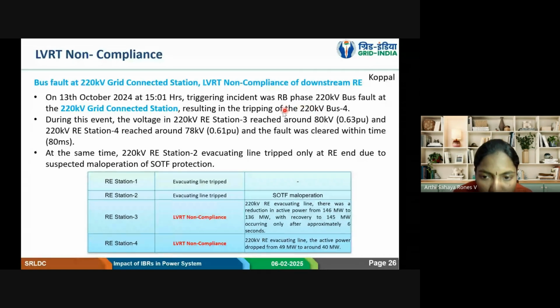Whereas, when we look into the voltages of the other RE stations during this fault, RE station 3 reached up to 80 kV, according to 0.63 pu, and in RE station 4 the voltage went up to 0.61. The fault got cleared within 80 milliseconds. So again, these are also within the LVRT curve. But we saw that one of the RE evacuating lines got tripped on operation of SOTF protection, switch on to fault protection.